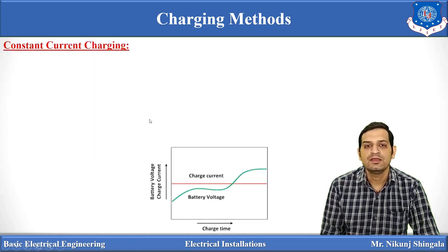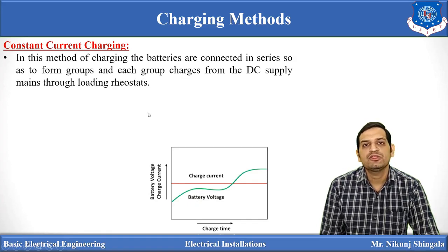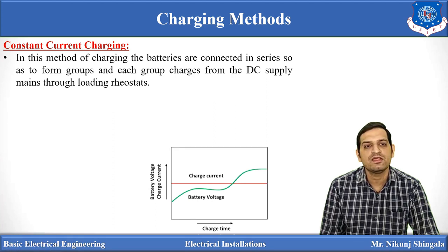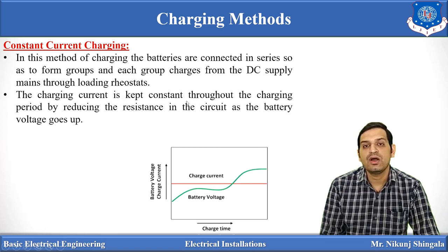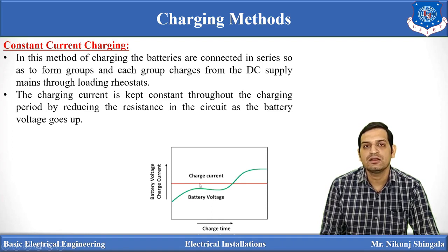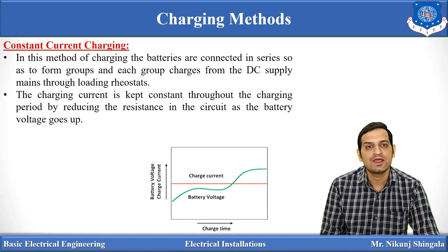In the constant current charging method, current is kept constant and voltage is varied. Batteries are connected in series to form groups, and each group is charged from a DC supply through a variable resistance rheostat. The rheostat value is reduced as battery voltage rises, to maintain a constant charging current throughout the process. The disadvantage of this method is that it takes more time compared to the constant voltage charging method.